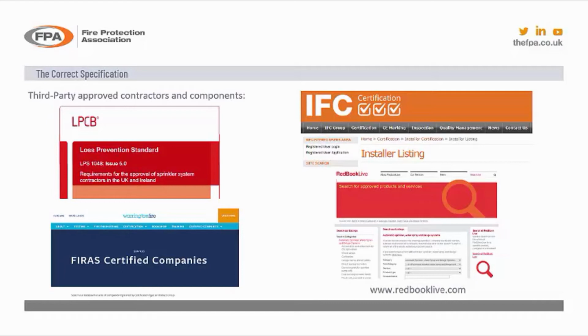And finally, bottom right there, we show the Red Book Live. Sprinkler components in the UK to both BS EN 12845 and also the LPC rules must be approved components, and these are LPCB approved components that must be used on sprinkler systems to the UK standards. If you have an American standard to NFPA or FM Global data sheets, they have to be FM approved, and they have different listings, different requirements, different approvals. But within the UK, the majority of sprinkler components need to be LPCB approved, which is part of the BRE. And they have the Red Book Live website, which allows you to go on there to look for approved components.